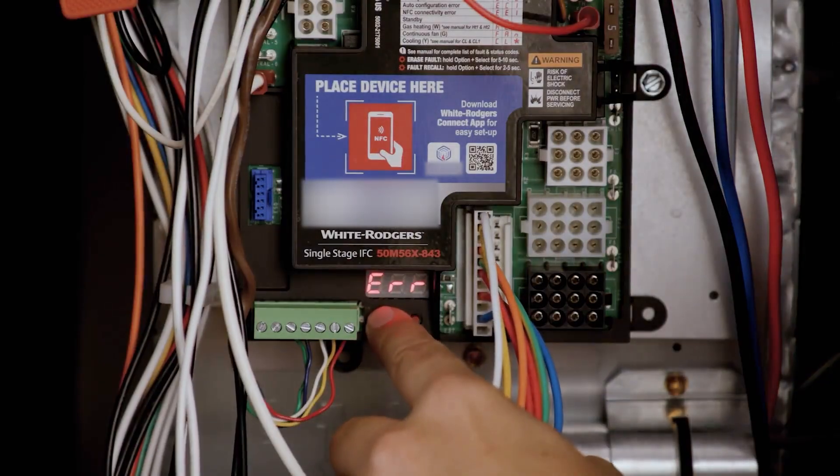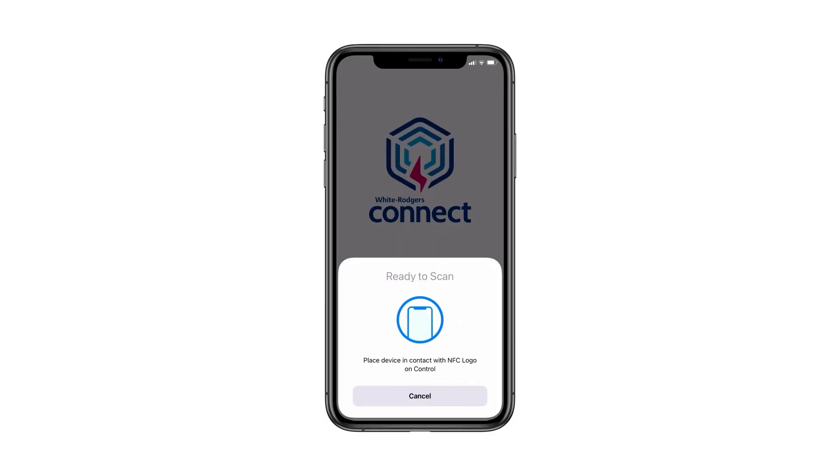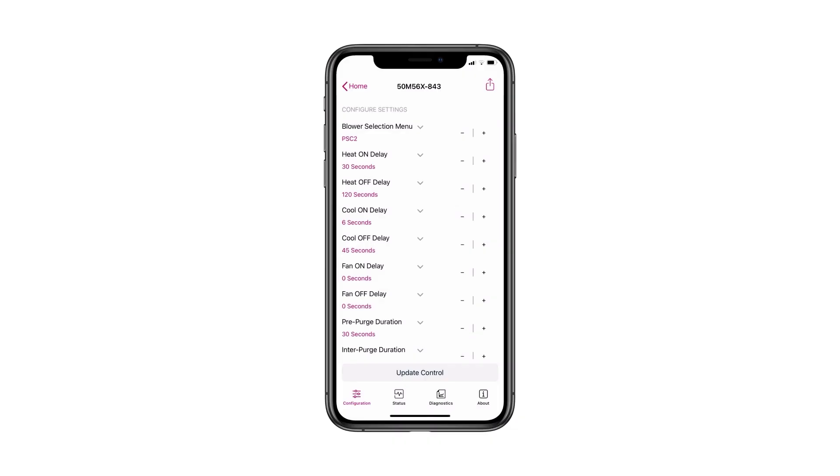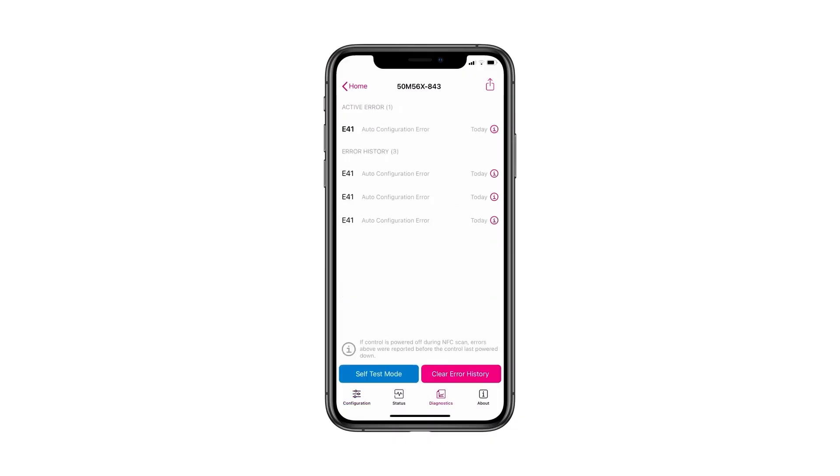Codes can be viewed and cleared directly from the control. Additionally, the White-Rodgers Connect app offers a diagnostic tab. You can also view and clear all error codes from this screen.